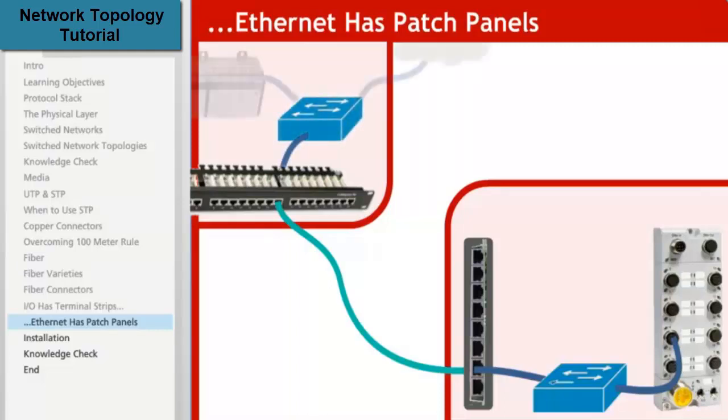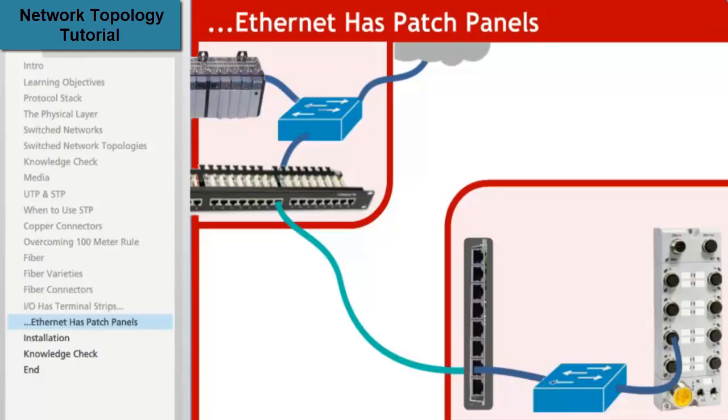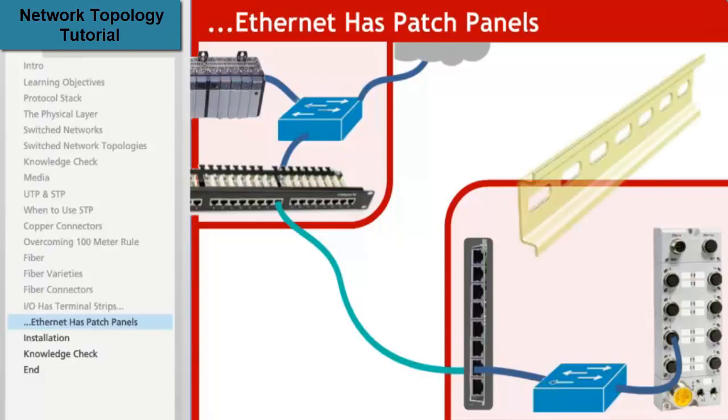It's a good idea to make sure that all fiber and copper cables entering a panel are terminated at a patch panel. In that way, panels can be completely tested, independent of the long external interconnections. The switch and end devices will not need to be touched during commissioning. Patch panels are available in different sizes and mounting options, including DIN rail.